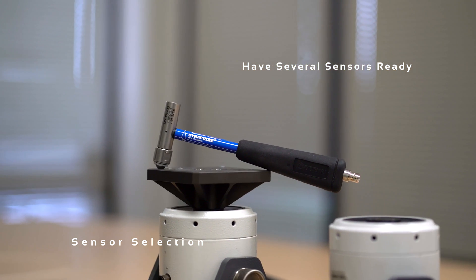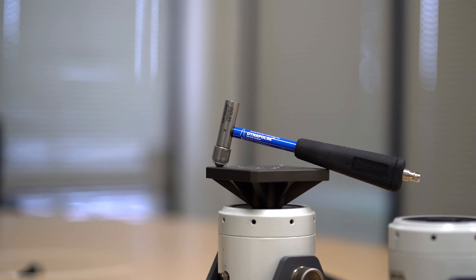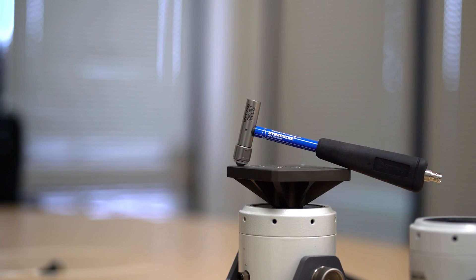It would be helpful to have a few impact hammers with different sensitivities and different weights. Another consideration is whether to use a few sensors which will be roved over the structure, or to use enough accelerometers so that all sensors can stay on the structure during measurements. The choice is often limited by lab budget, but it's often necessary to use the latter approach to obtain top quality results.